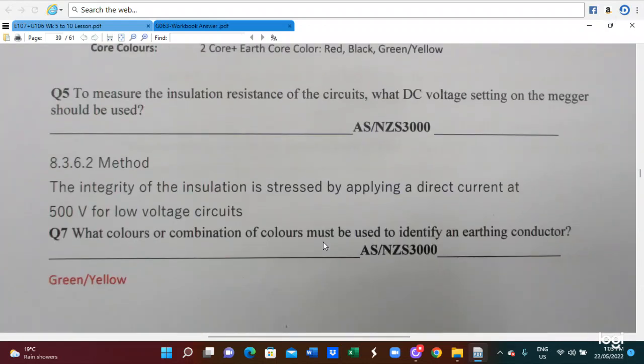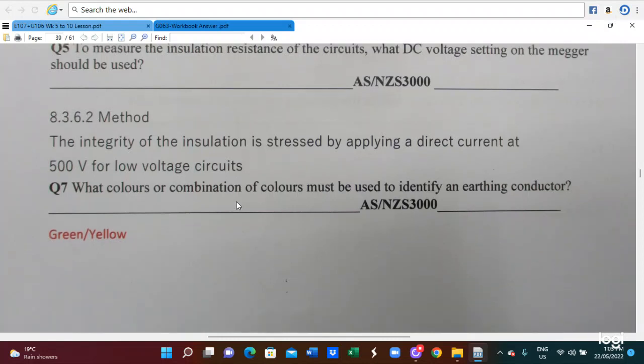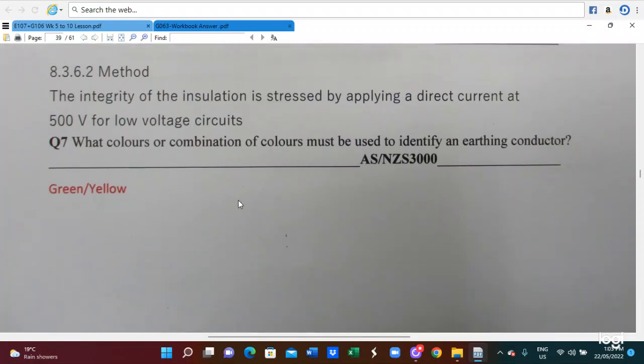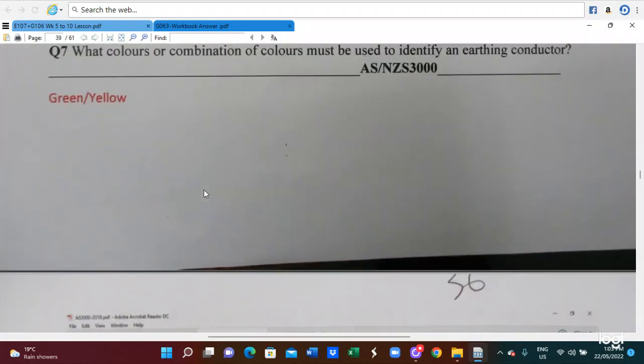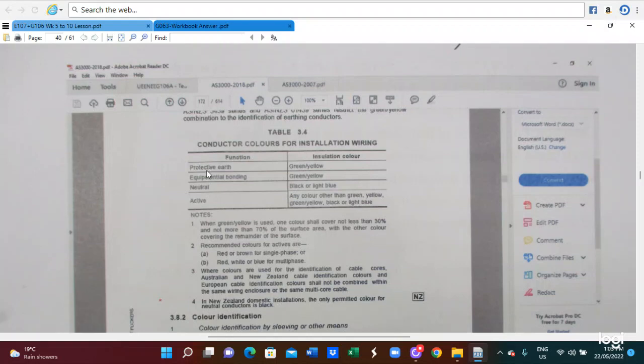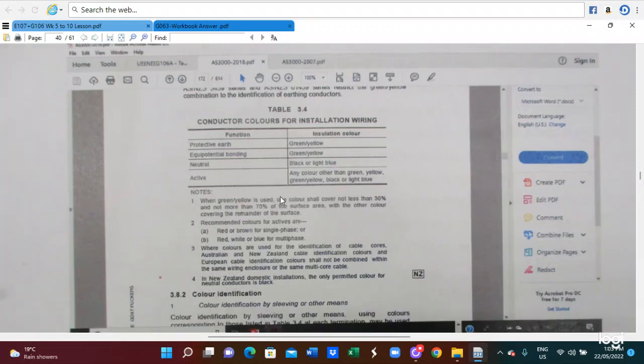To measure the insulation resistance of the circuit, what DC voltage setting on the megger should be used? The answer is in 8.3.6.2. We have to use 500 volt. What color or combination of colors must be used to identify the earthing conductor? The answer is green-yellow. The reference is Table 3.4 of the AS/NZS 3000.